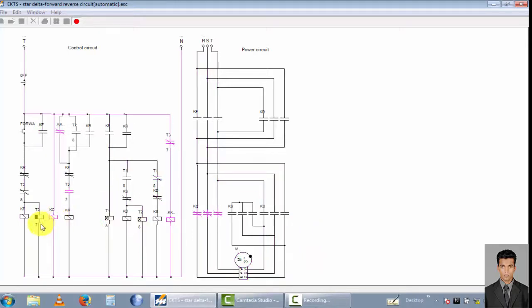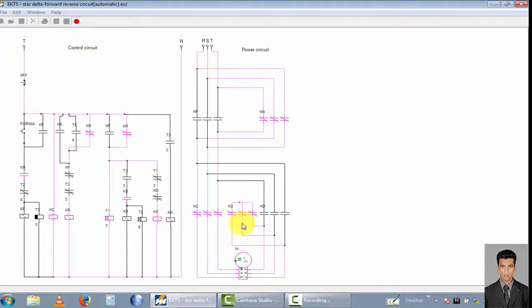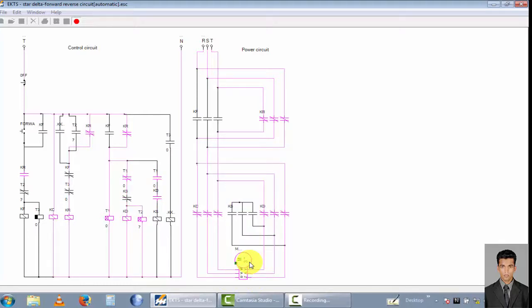This is the off-time delay. After 8 seconds, the motor starts in the reverse direction in star condition. You can see the motor is now rotating in the reverse direction. After a few seconds, the motor changes to the delta connection and rotates continuously in the reverse direction.